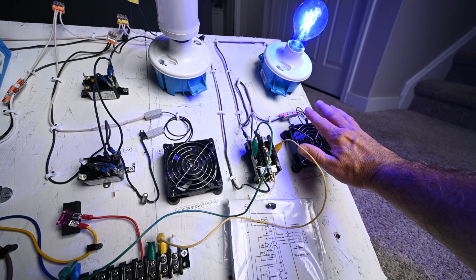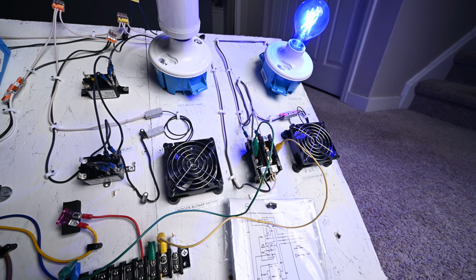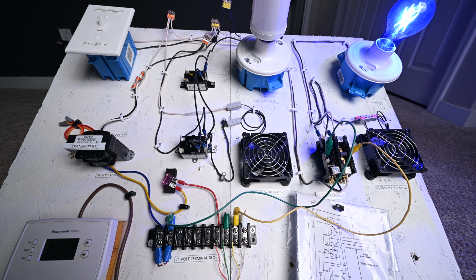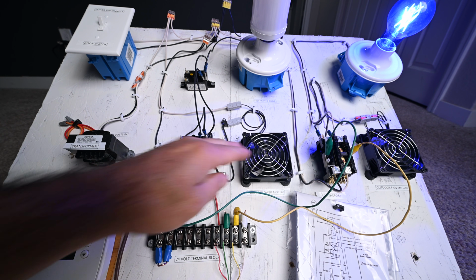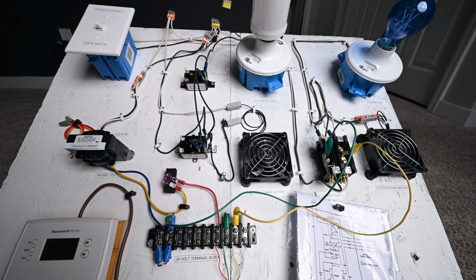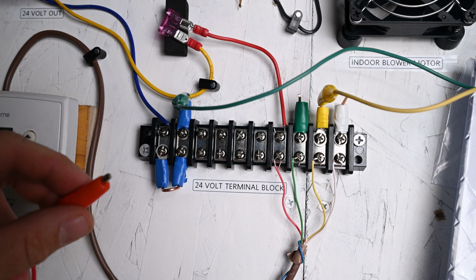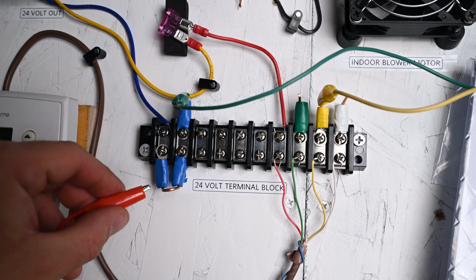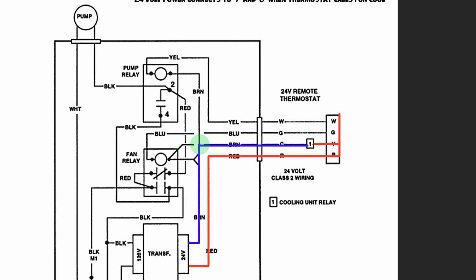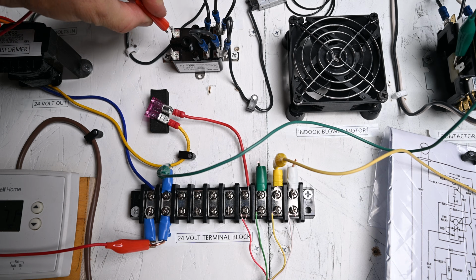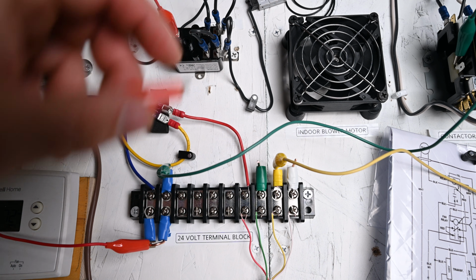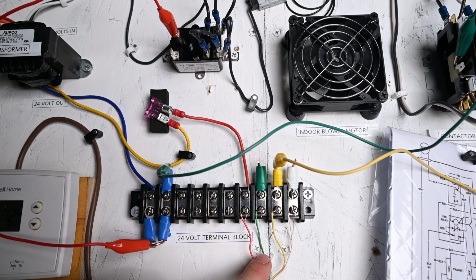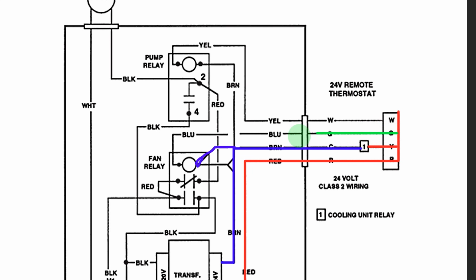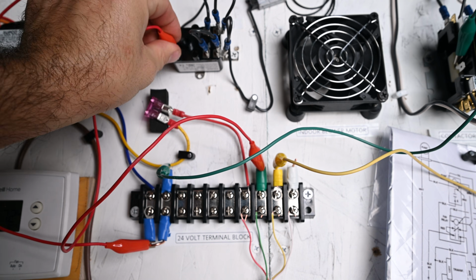Our light's on, and it's hard to see, but our fan is also on, simulating a real-life scenario. But if this were a real-life scenario, then our unit would freeze up because our indoor blower motor is not running. Let's hook that up. Turn the power off. Each one of these switches that uses a coil to energize them needs a common, and they need 24 volt power. I've got one alligator clip on common again, and the other to either side of this 24 volt fan relay coil. Next, I'm going to go to my green terminal, the green wire, which is fan in this case. Hook that up, and then hook my other side of the alligator clip up to the other side of the fan relay coil.